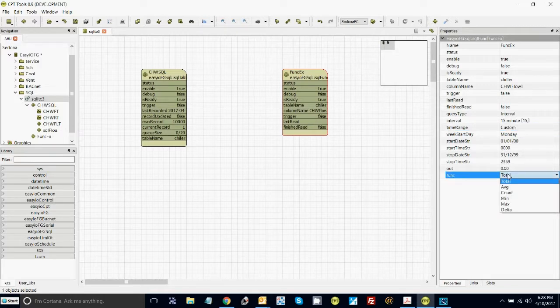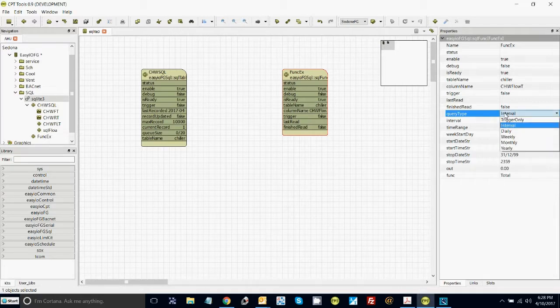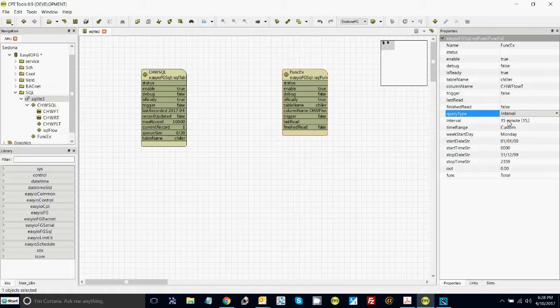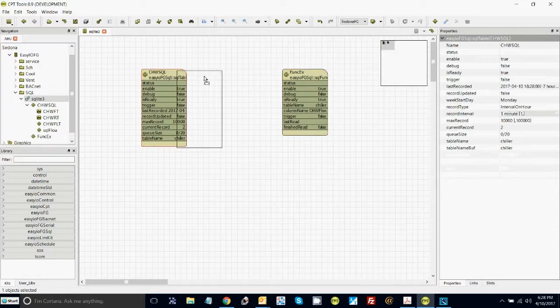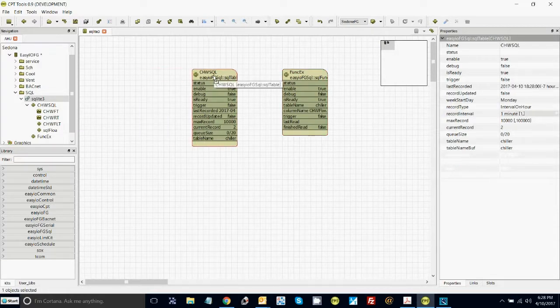The function output can be an average, a count, a min, max, or a delta. You can do it on an interval or a trigger — daily, weekly, yearly. When it does activate based on what you've said, you will get a value here. I've got a little trick to show you — a way I've come up with to make this work. Inside here we've got two ramp objects simulating chilled water flow and chilled water return, basically sine waves so the values are going up and down within a certain range.